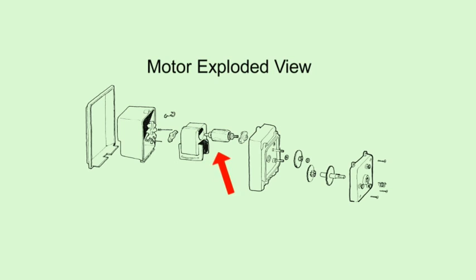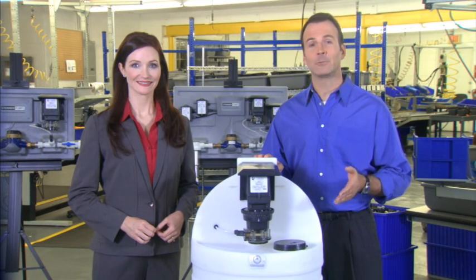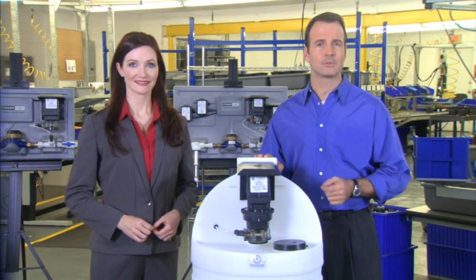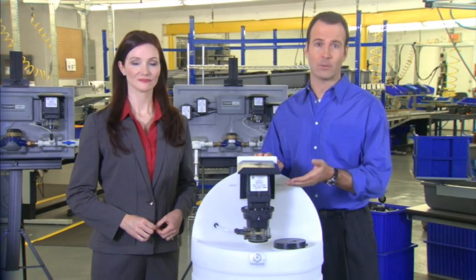When power is applied to the coil, the rotor rotates. The rotor's directional rotation is determined by the orientation of the copper-shaded poles on the coil. The helical end of the rotor engages the series of gears in the gear case. A vertical mount with the pump head in a downward position is recommended to keep chemical from collecting in the tube housing and from seeping into the feed rate control and/or the motor.